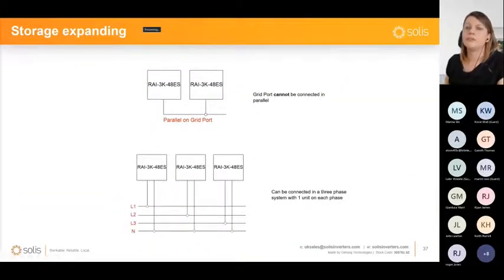Quite useful. What I have to mention here is that for now, these units cannot be paralleled on the grid port, for a reason that is very obvious. If they're connected to the same connection point, their meters will always monitor two times the energy that is going through that connection point, and they're going to fight with each other for that same energy. So for now, these cannot be paralleled. What you can do, if you have a 3-phase system, is connect one inverter on each phase on the main AC port, but not on the backup port. You cannot create a 3-phase emergency power supply with them. So just on the main AC port, if it's really needed.